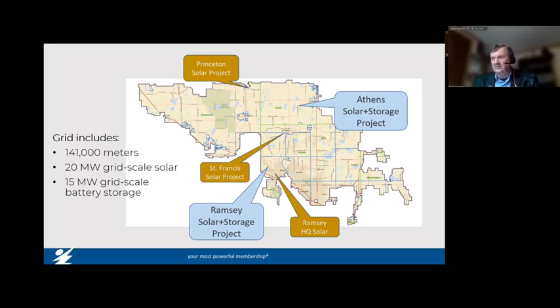In terms of renewables, we actually have 5 different sites. We have our 240 kilowatt solar garden in the front yard of our office space in Ramsey. We have 2 sites of solar plus storage, one in Ramsey, where the field tour was, and another in Athens, about 2 miles south of the city of Isanti. We also have 2 other solar-only installations without batteries, single tracking solar systems, one just south of Princeton and the other just northwest of St. Francis. That ends up being 20 megawatt capacity total of solar, and the batteries at the Ramsey and Athens sites total 15 megawatts of grid scale capacity, 2-hour batteries, so that's 30 megawatt hours of energy. Those are the 2 systems we're going to focus on today, and what this slide deck will cover.